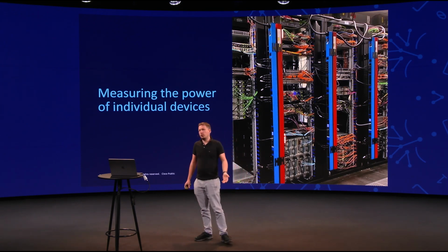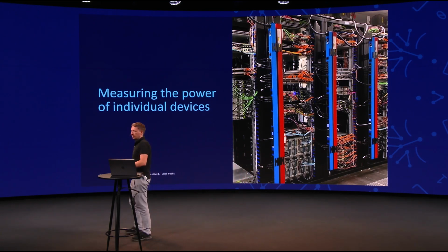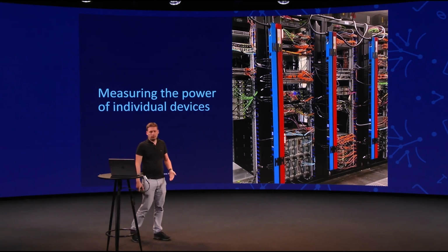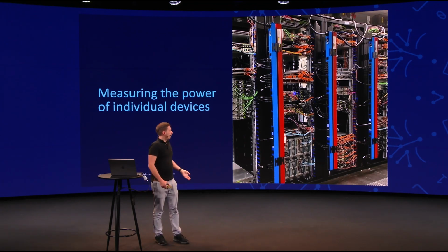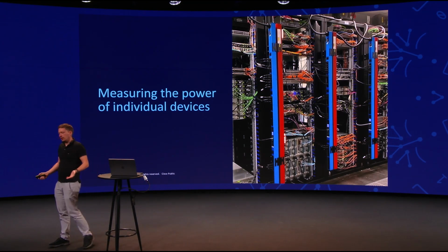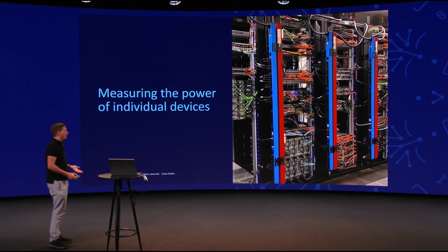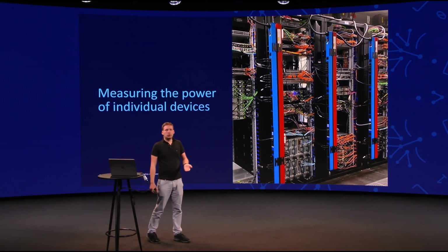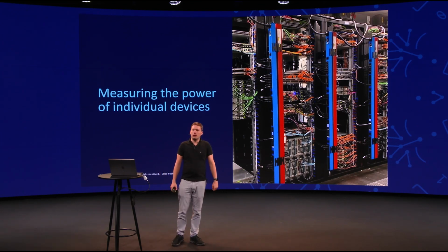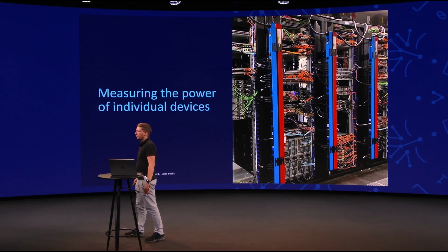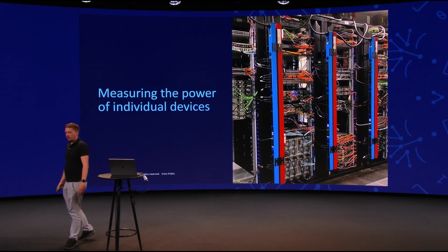You can use a power sensor to approximate that, but then you have to take relatively granular measurements, because you can only approximate based on these measurements, but you don't actually know in detail what the device consumed every second, because you're usually not measuring every second. That's one of the downsides. So there will be some small accuracy losses, and of course we also have to consider that each power sensor has a certain error tolerance in terms of what it's measuring. And last but not least, there's also the factor that we are consuming power in our devices, but we are producing heat, and so whatever we use for cooling in terms of energy, we have to, at some point at least, also account for when we consider the individual power consumption of our devices.